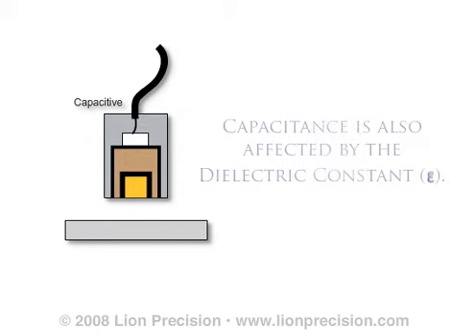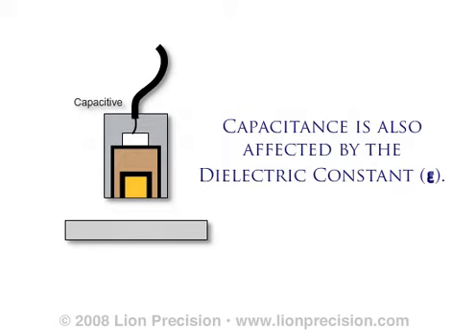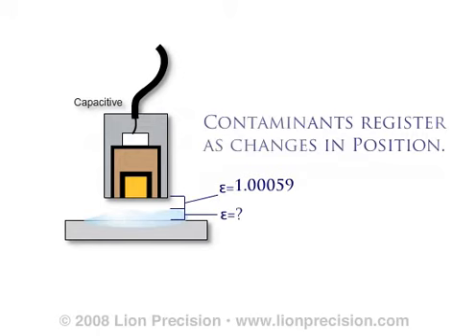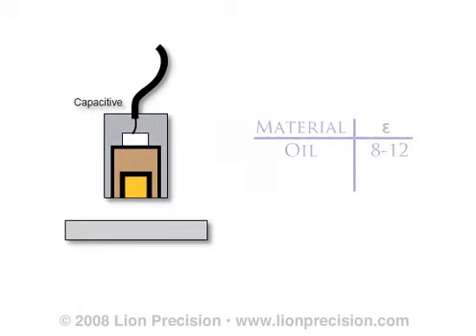Another factor that affects capacitance is the dielectric constant of the material in the gap between the target and sensor. The dielectric constant of air is slightly greater than 1. If another material with a different dielectric constant enters the sensor-target gap, the capacitance will increase, and the sensor will erroneously indicate that the target has moved closer to the sensor. The higher the dielectric constant of the contaminant, the greater the effect on the sensor. Oil has a dielectric constant between 8 and 12. Water has a very high dielectric constant of 80.